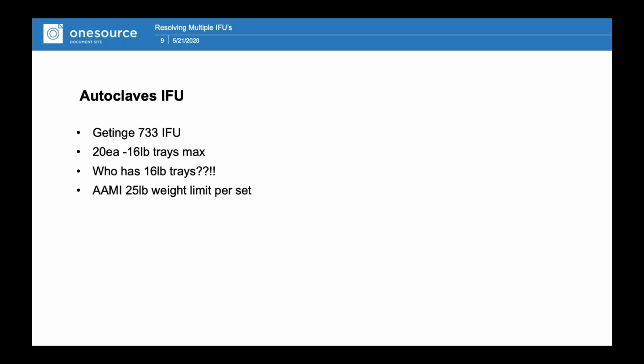But let's dig a little further and talk about this more in depth. Why 20 16-pound trays? An autoclave vessel, by the way it works, has steam come into the chamber and condense. The steam transfers its energy into the instruments and collapses back into water, and that's condensate. So the trick of sterilization is that the entire load is soaking wet with water during the come-up phase and the exposure phase. Then when it's done with the sterilization cycle, we have to re-evaporate that liquid condensate. We have to dry the load.